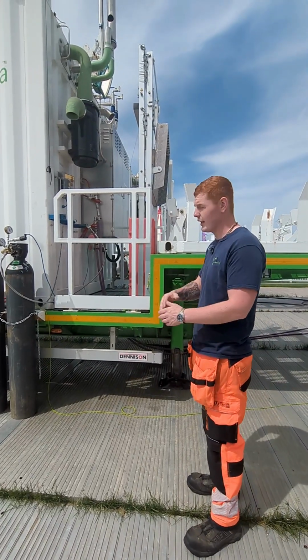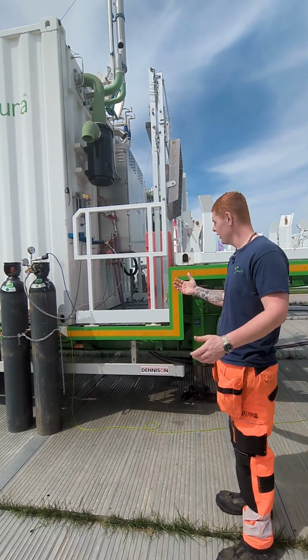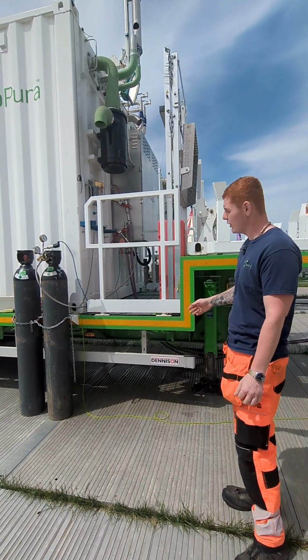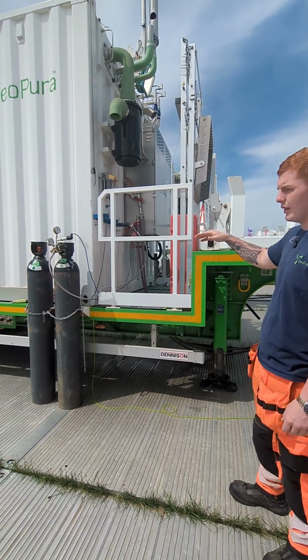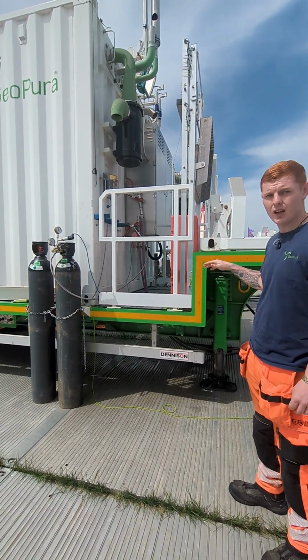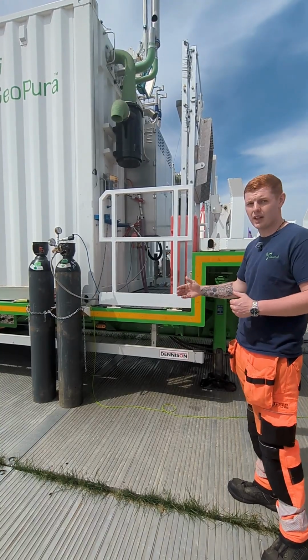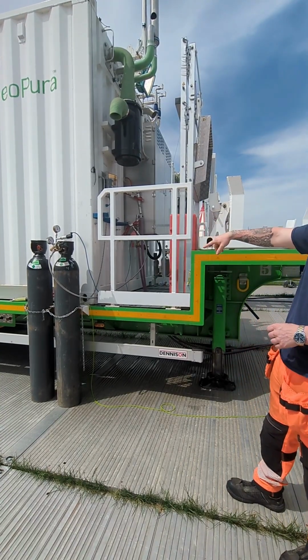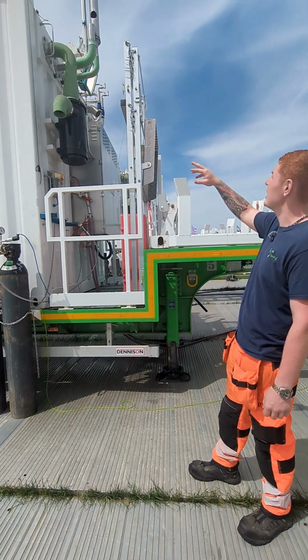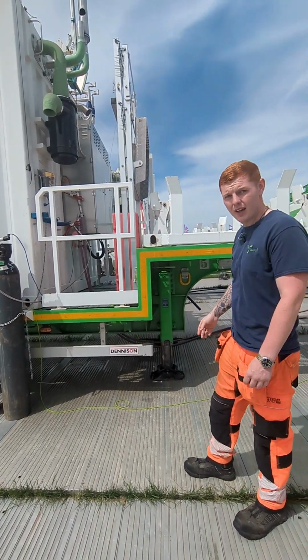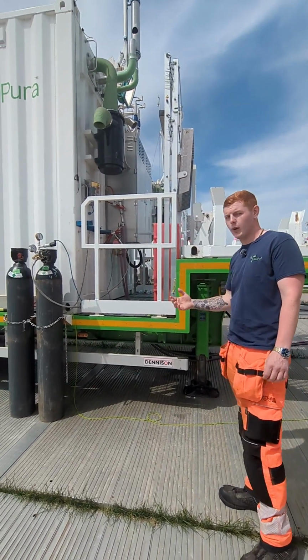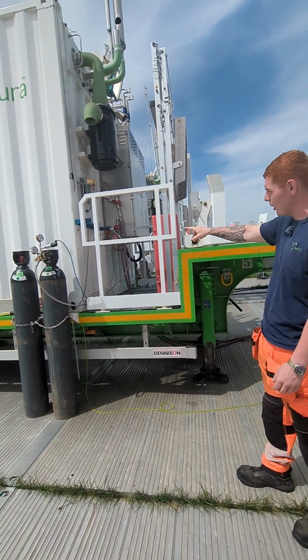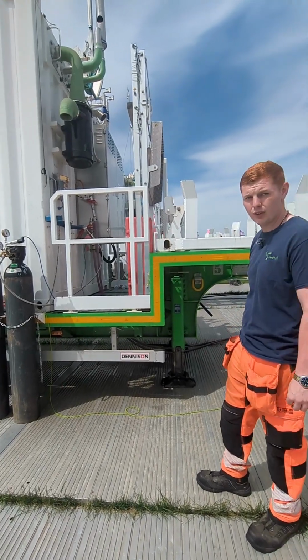When the site load increases and when it's humid, it obviously creates a lot more water. To be honest, the load they're doing is maybe half each. If they were doing 75-80% each, you wouldn't see as much water coming out of this, as most of it would get turned to steam and come out the top of the vents. So the hotter it is, the more chance of it coming out as steam, and less from the overflow.